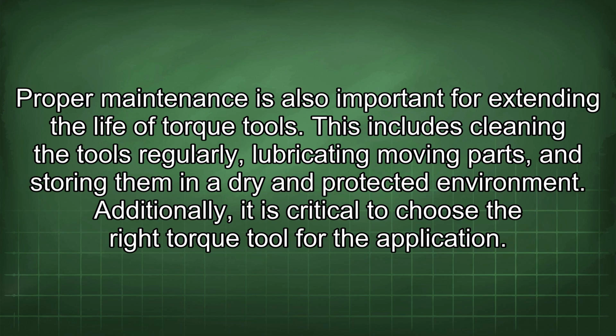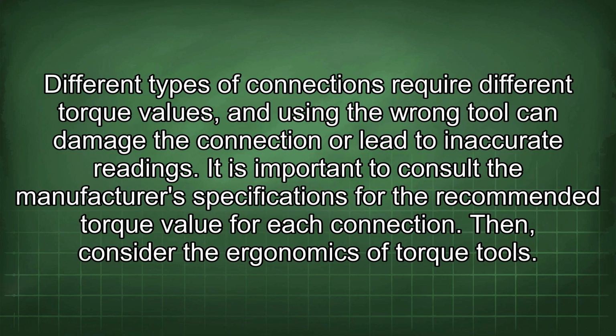Additionally, it is critical to choose the right torque tool for the application. Different types of connections require different torque values, and using the wrong tool can damage the connection or lead to inaccurate readings. It is important to consult the manufacturer's specifications for the recommended torque value for each connection.